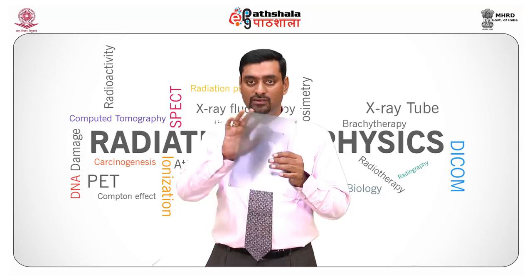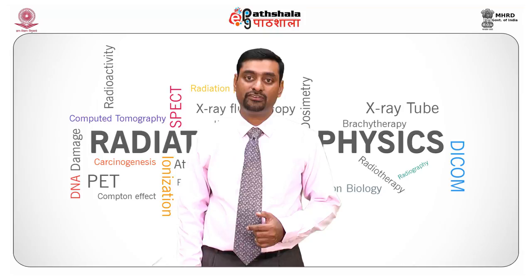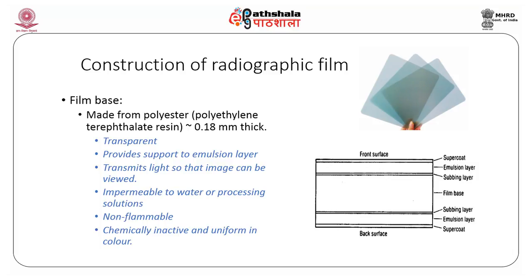Let us get into detail about the construction of a radiographic film. The film base is made out of polyester which is approximately 0.18 millimeters in thickness. The film base should be transparent, provide support to the emulsion layer, transmit light so that the image can be viewed, be impermeable to water or processing solution, non-flammable, chemically inactive, and uniform in color.